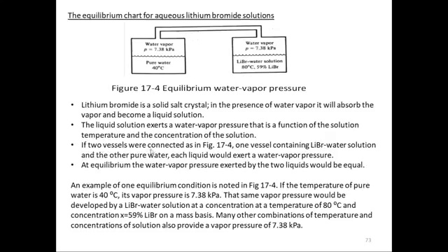Okay, if two vessels were connected as in figure above, one vessel containing lithium bromide water solution and the other pure water, each liquid would exert a water vapor pressure. At equilibrium, water vapor pressure exerted by the two liquids would be equal.